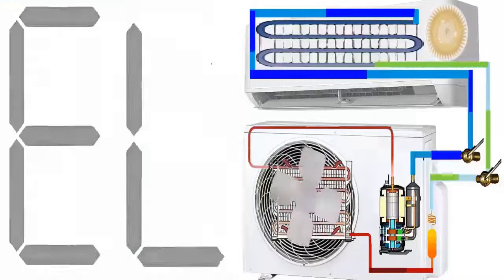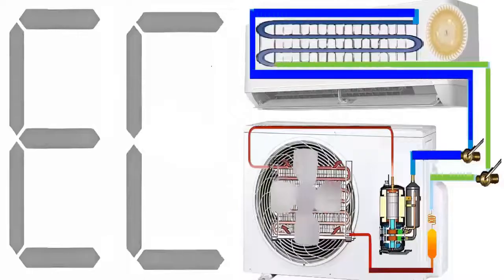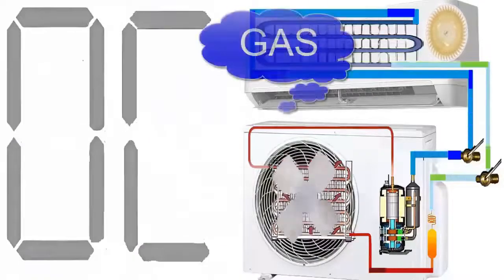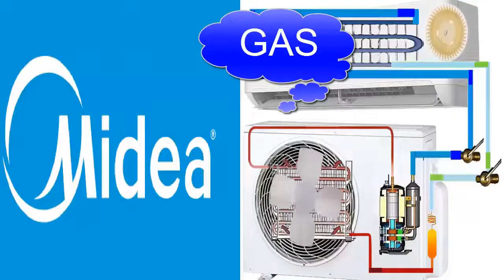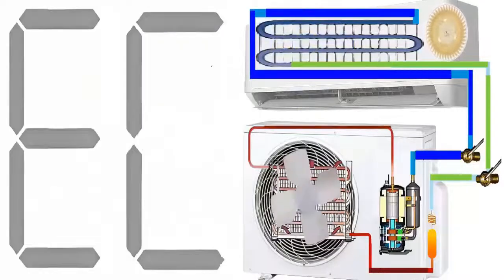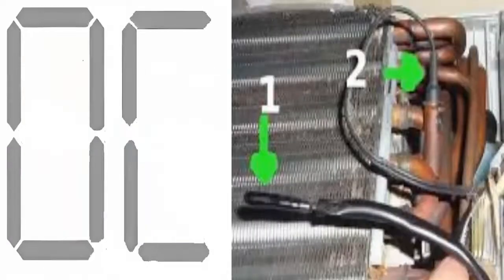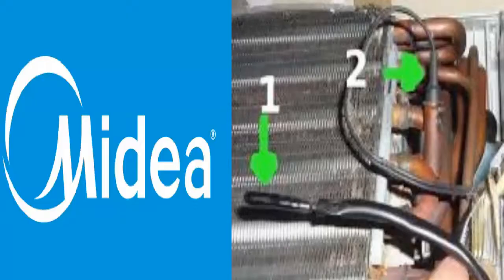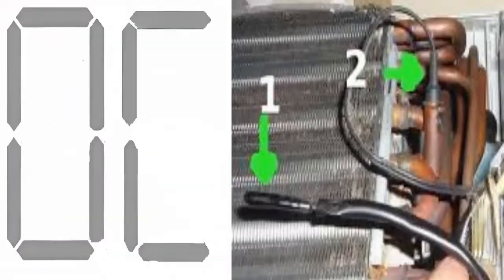The error code EL0C or EC in Midea air conditioners is activated when the system, through its control strategy, detects a possible refrigerant gas leak. However, this code can also be triggered by other factors. For many Midea models, the control strategy for detecting a refrigerant gas leak is based on comparing the values recorded by the temperature sensors, especially the sensor located on the coil of the indoor unit.